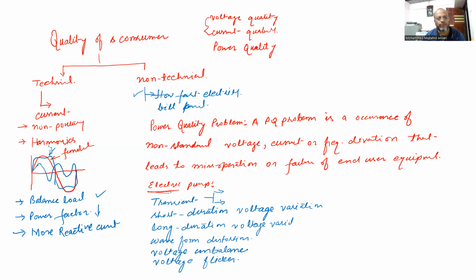Waveform distortion: the waveform is not sinusoidal, but somewhere it is a square, just like a square wave. Voltage unbalance is because of single phase loads, a large number of them. It may be a welding transformer, an electric furnace, or welding machines, a large number of welding machines and electric furnaces. So it will definitely make the system unbalanced, or cause voltage flicker. These are some problems called power quality problems.